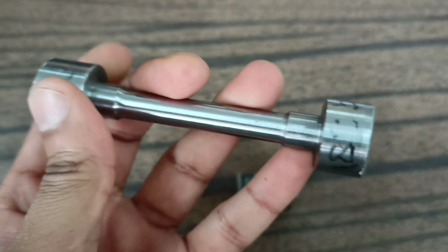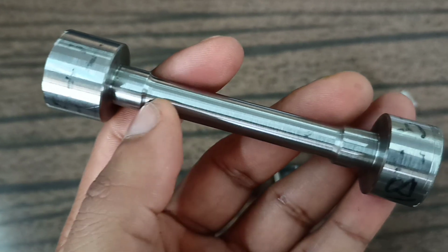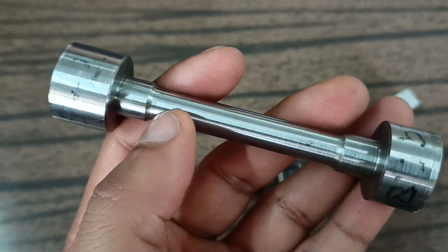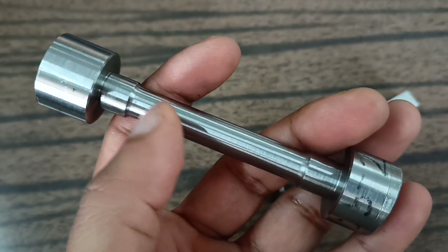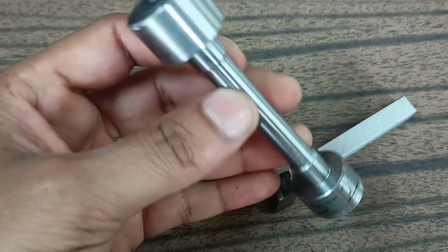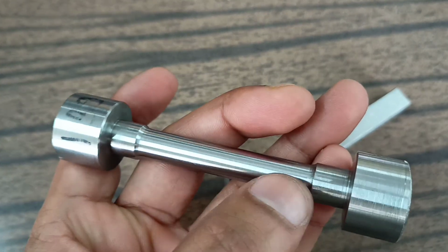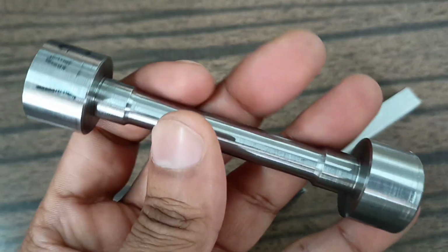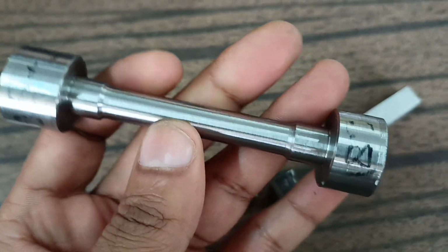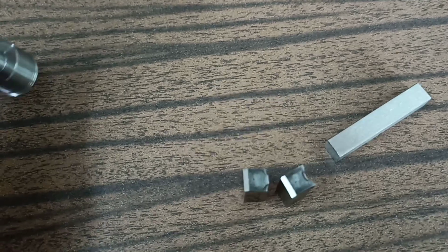These are two arrangements to be held in the machine, and in the middle portion you can see the area where we mark the gauge length. We mark two points, one point here, the other point here, and we mark it as the gauge length, and further we place it inside the machine. We also place an extensometer over here, and with this extensometer we measure elongation up to the yield strength. So this is it.